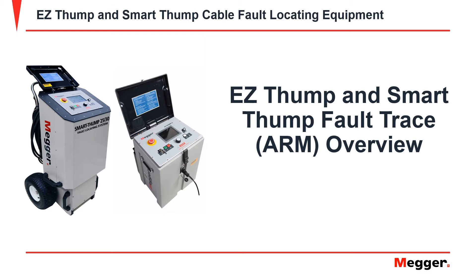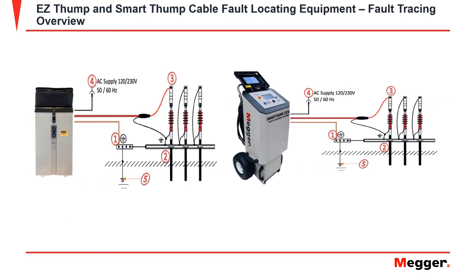In this video, we will be going over the fault trace or arm on the easy thump and the smart thump. For a brief connection overview: first, apply your equipment safety ground to ground. Then, apply your high voltage return lead to the concentric neutral or shield under test. Finally, place your high voltage output lead to the cable under test.